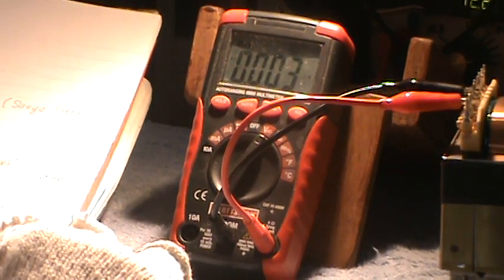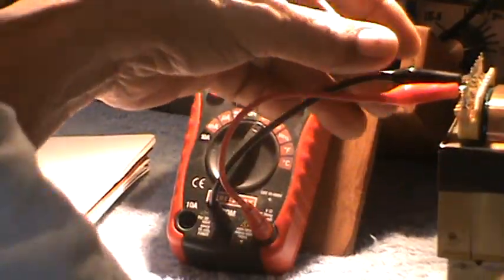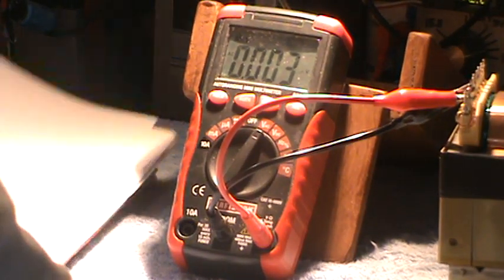The next one is 8 and 9. Yes, to be safe, I remove the plug. 8 and 9. This is terminal 8. This is terminal number 9. Okay, we are measuring AC voltage, so there's no polarity. We could interchange the black and red. Okay, 8 and 9. A while ago, I measured the resistance between terminals 8 and 9 of 0.3 ohms. And supposed to be, we could measure a voltage across it.